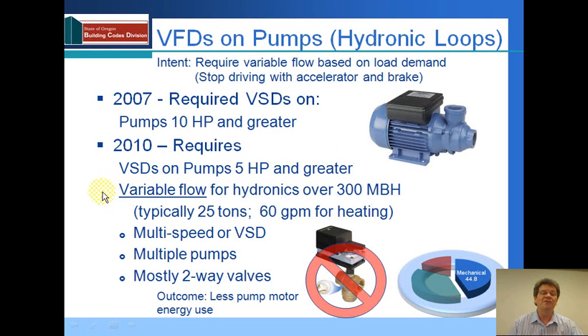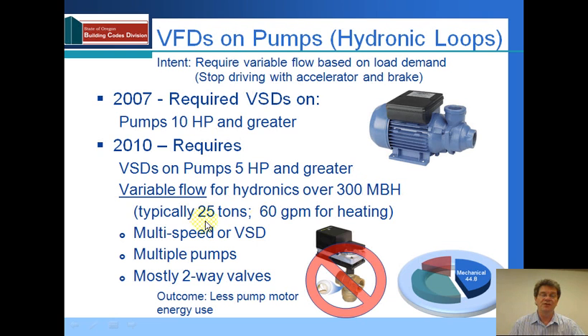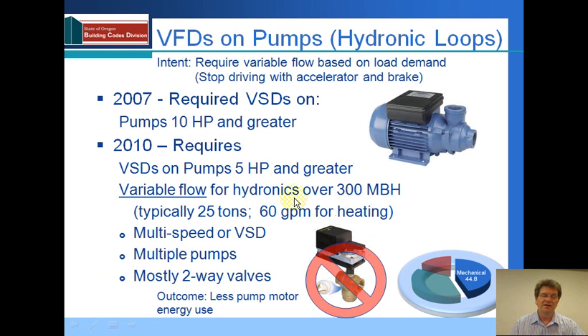There's also a new requirement for variable flow. The old requirement had variable speed drives required when there was variable flow. The new requirement says you shall have variable flow whenever you've got a system larger than 300,000 BTUs per hour — typically 25 tons of cooling or about 60 gallons per minute on a heating water pump. There's also a requirement for multiple speed, variable speed drive, or multiple pumps. As far as compliance, it's mostly going to involve two-way valves. If you see a system where all the valves are three-way valves, that is probably not a compliant system unless it's smaller than these limits.